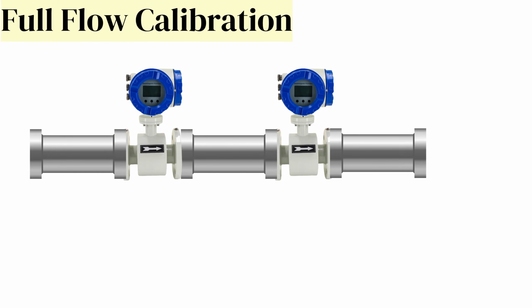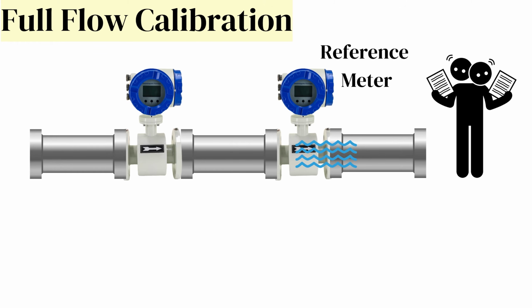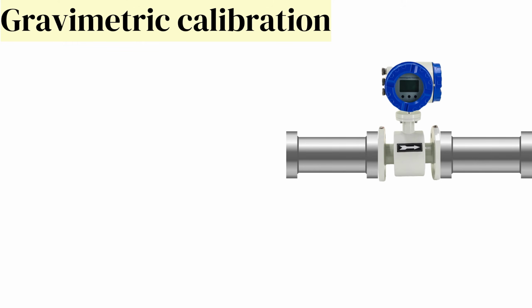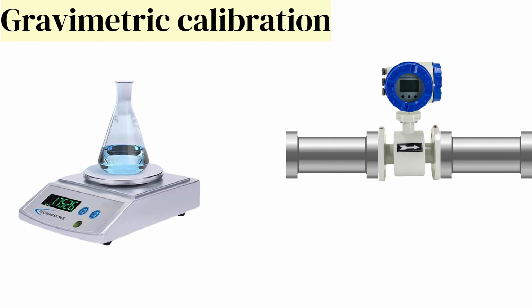1. Full flow calibration. This method uses a calibration facility where the flow meter is installed in a test loop. A reference meter of known accuracy measures the flow rate, which is then compared to the electromagnetic flow meter's readings. 2. Gravimetric calibration. In this method, the fluid is weighed before and after it passes through the flow meter. The difference in weight over time gives the actual flow rate, against which the flow meter's readings are adjusted.